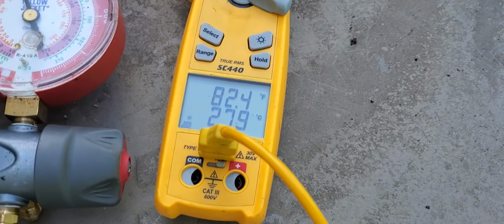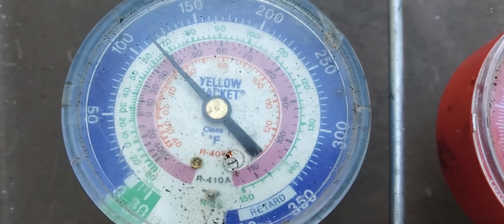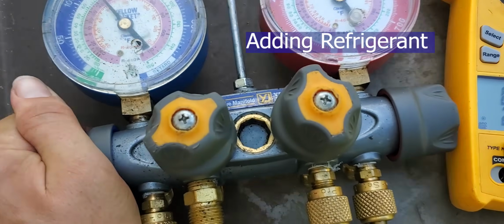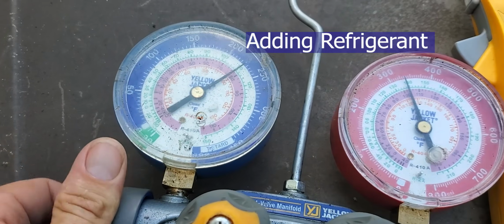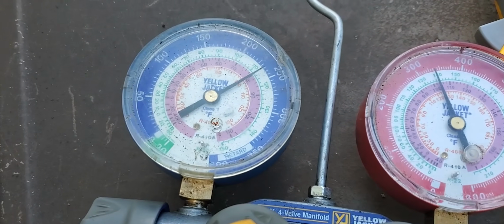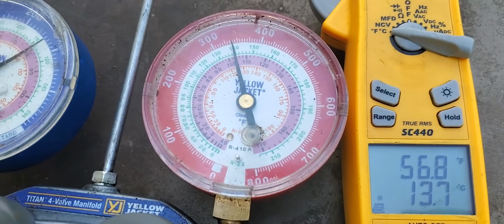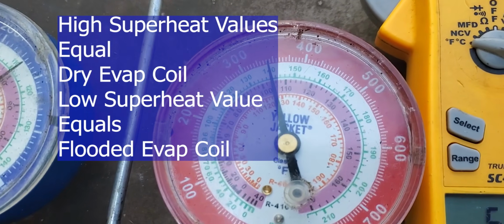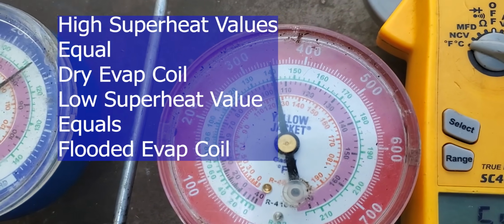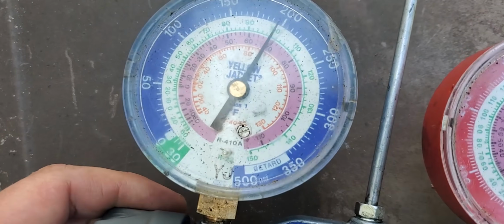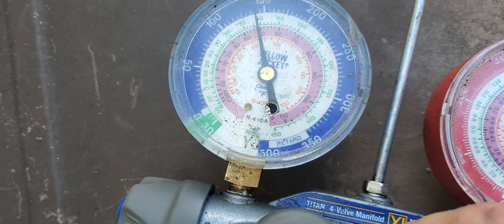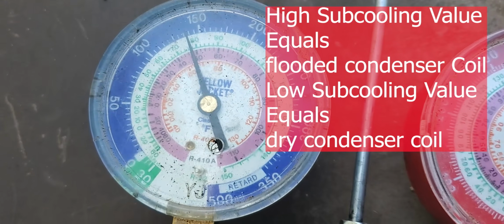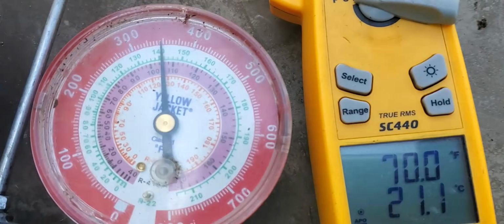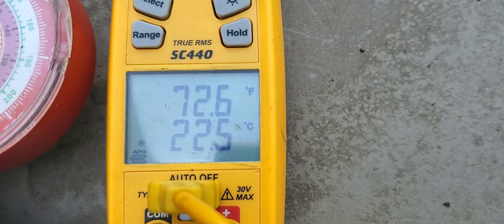I want you to think about each coil individually and think about them being dry, which means they don't have enough refrigerant, or being flooded, which means they have a lot of refrigerant. And I want you to make sure that you understand that if I have a superheat that's 100, then that means I need to add more refrigerant. If I have a superheat that is 0, then I have too much refrigerant. And I want you to also understand that if I have a subcooling that is 30 or 40, that means I have too much refrigerant. And if I have a subcooling that is 1 or 0, that means I don't have enough refrigerant. I want you to make sure you get that in your head before we move forward.